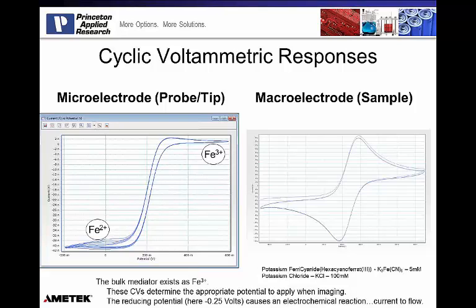So here we have the cell comprised of a 5 mm gold disc. We're working with a probe that is a 25 micron platinum probe with an RG ratio of 10. Then as a supporting electrolyte, we have 100 millimolar KCl. So in the image on the left, we have a typical sigmoid-shaped response of an ultramicroelectrode in a cyclic voltammetry experiment. When I created the solution, my bulk ion exists as iron 3+. That's important to know, because if I look at the oxidizing potentials, the positive potentials on the right, iron 3+ exists, and there's basically no electrochemistry happening at the positive potentials because I'm already starting with iron 3+ in the bulk state.